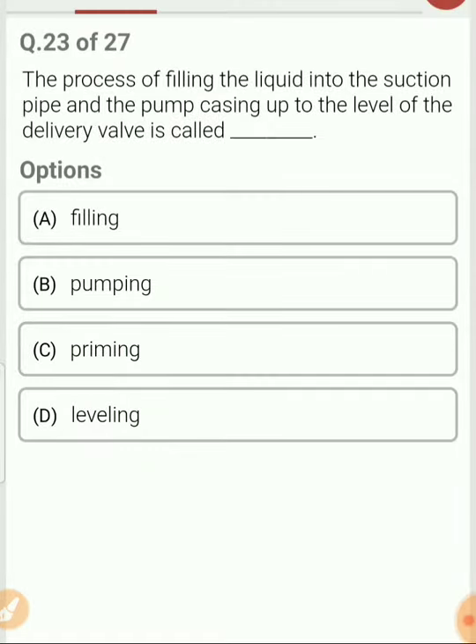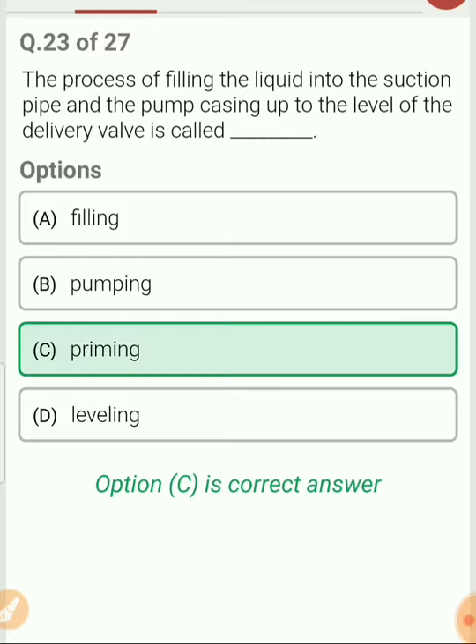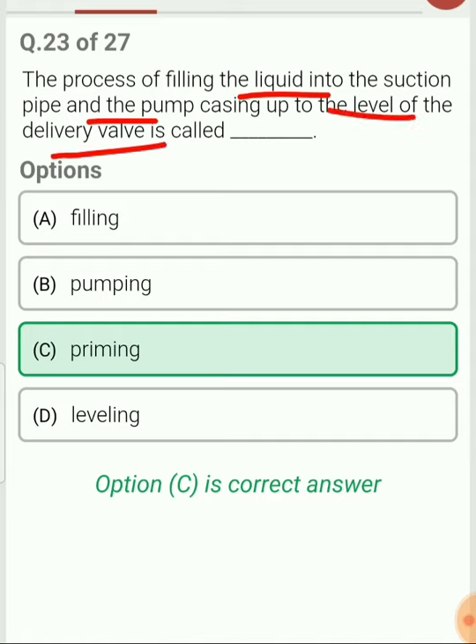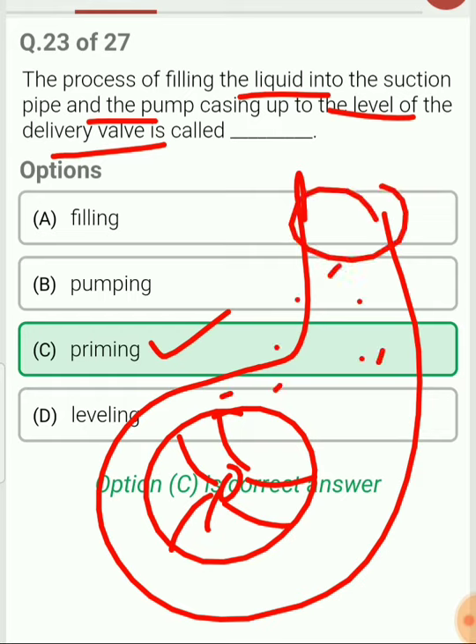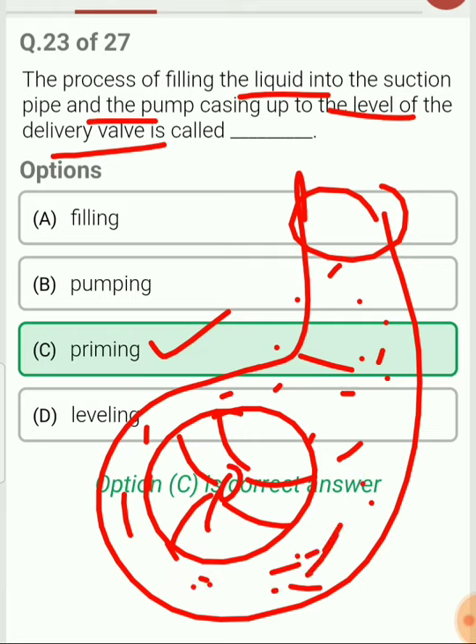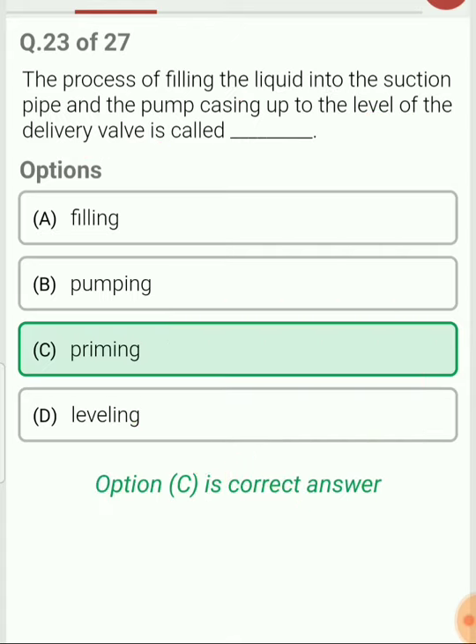The process of filling liquid into the suction pipe and pump casing up to the level of the delivery pipe is called priming. Before starting the pump we need to fill the pump with water. The definition: filling of liquid into the suction pipe and pump casing to the level of delivery pipe is called priming. Water is filled from an external source, and once filled, the impeller is started.